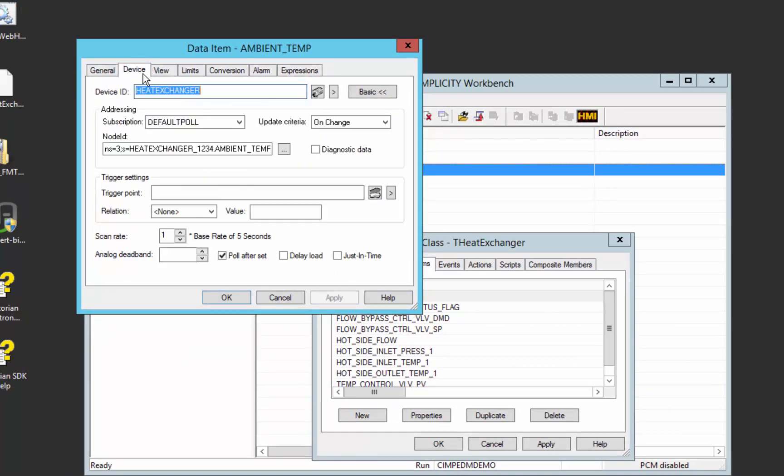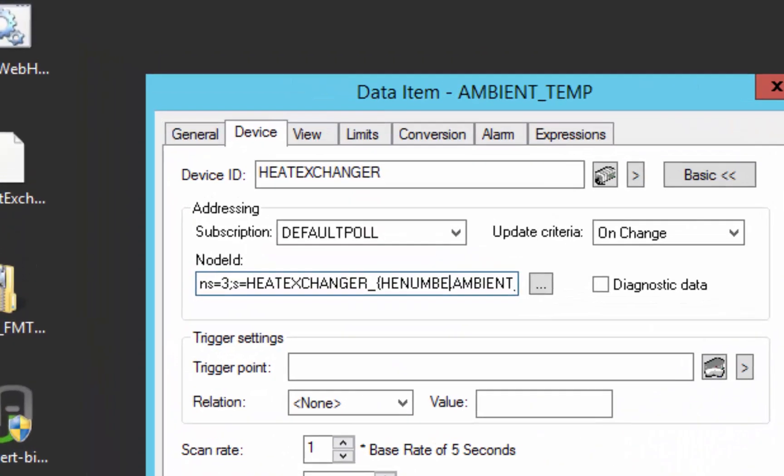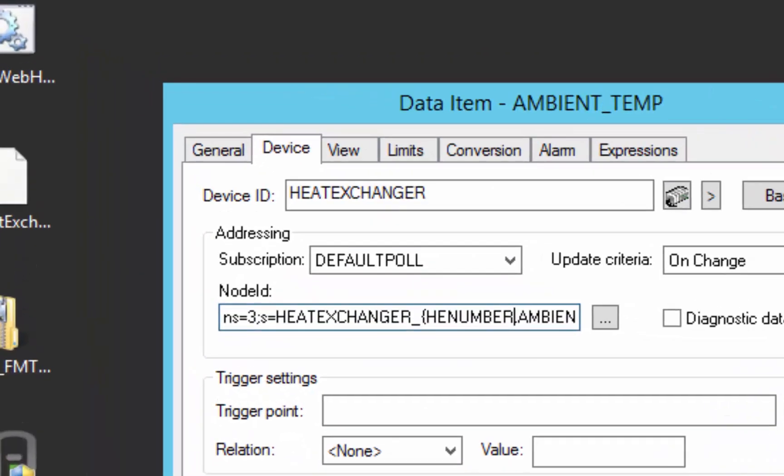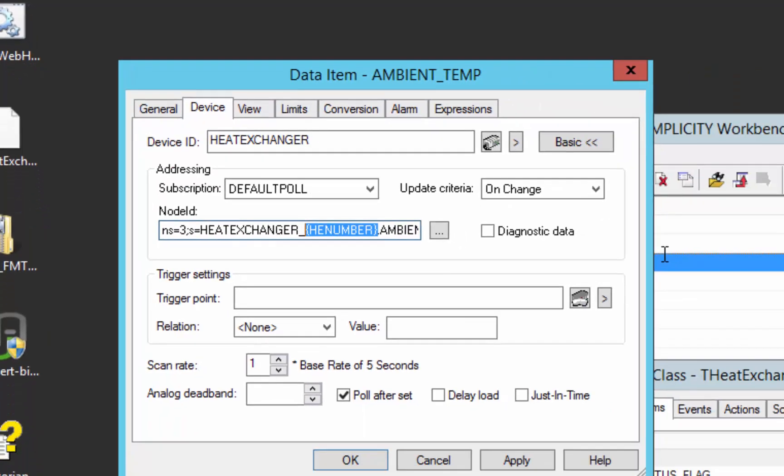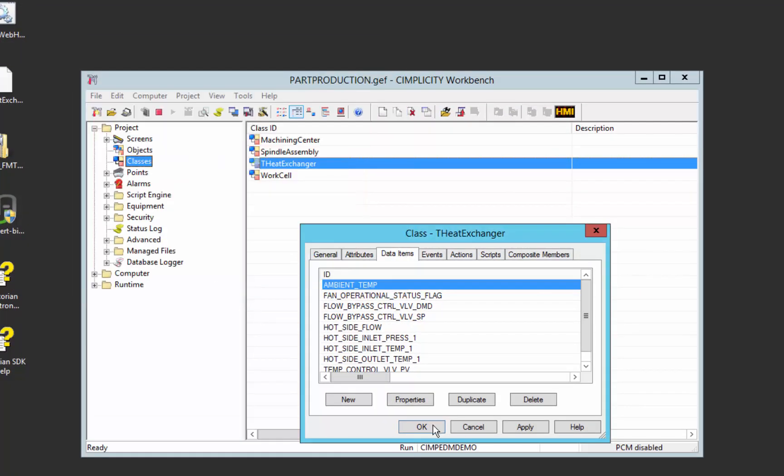As we just showed, we have 1234 here. But we want that to be dynamically substituted as we create objects. So I'm going to put HE number, the heat exchanger number, inside curly braces here. This becomes a substitutable value that will be replaced with the actual value of the instanced version of this asset when we create the object.